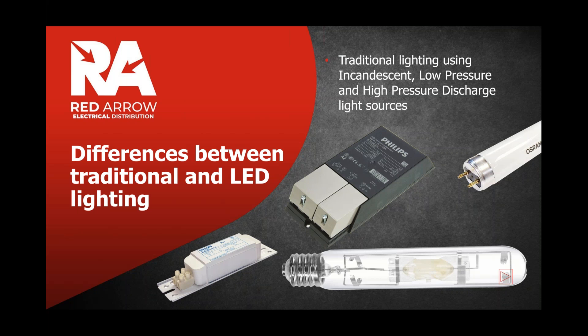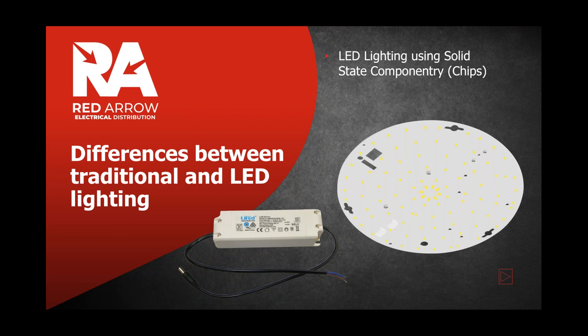Converting traditional light sources to electronic control gear — as shown in the slide with the Philips header — operated in a similar way, as it had some transformer components but was a hybrid with many electronic components too. Many of these had some kind of non-replaceable fusing device at the front end. The difference with LED lighting is it is solid state — instead of a gas-based discharge tube or filament to absorb a voltage spike, you have solid-state lighting components and solid-state electronic components within the drivers, very similar to the types of components inside mobile phones and computers.